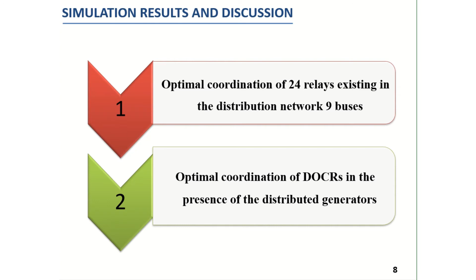In order to study the behavior of protection relay coordination in the studied system in the presence of the distributed generators, two scenarios are proposed. The first one consists in determining the optimal values of the parameters of the 24 relays existing in the distribution network interconnected with 9 buses using the genetic algorithm. The second one is the use of the genetic algorithm on the network containing the 4 generators to find new parameters and solve the coordination problem.